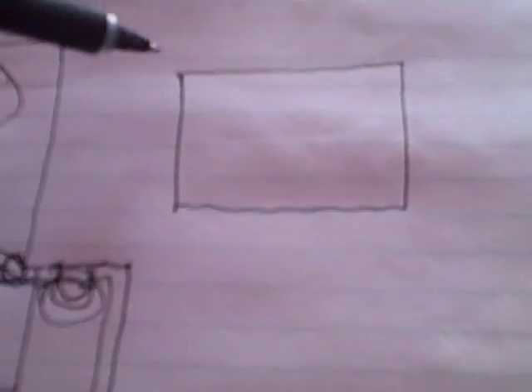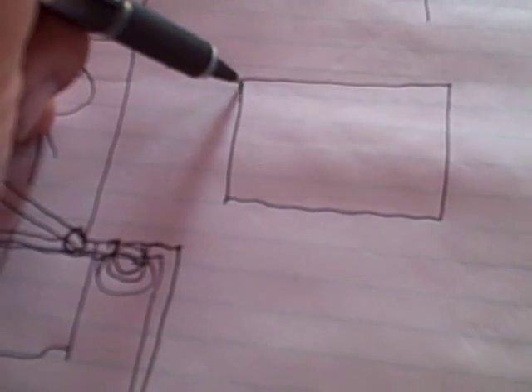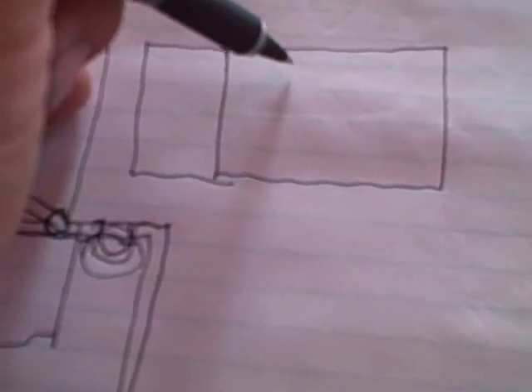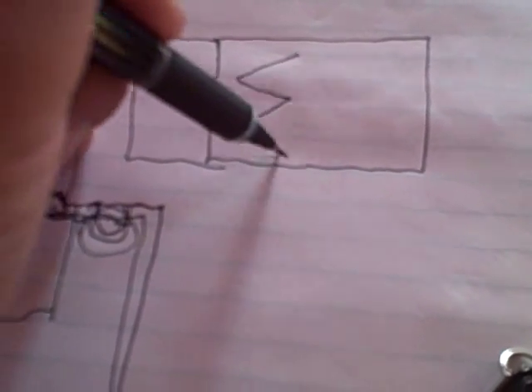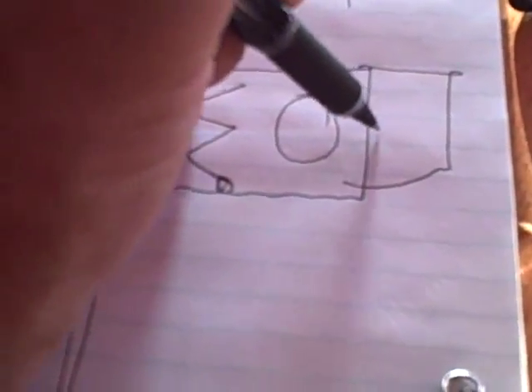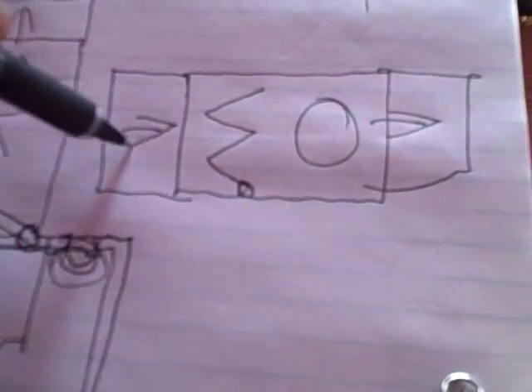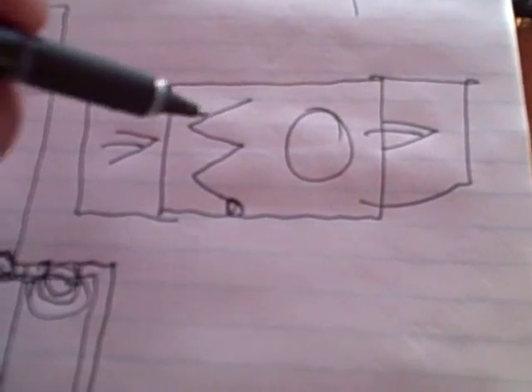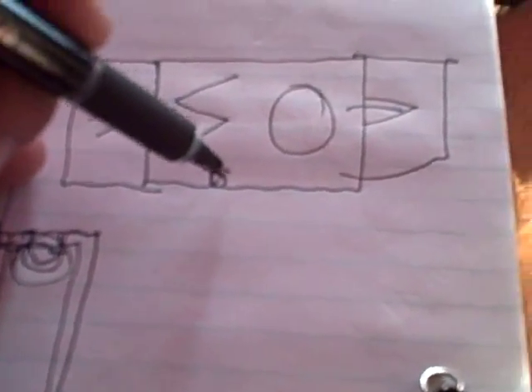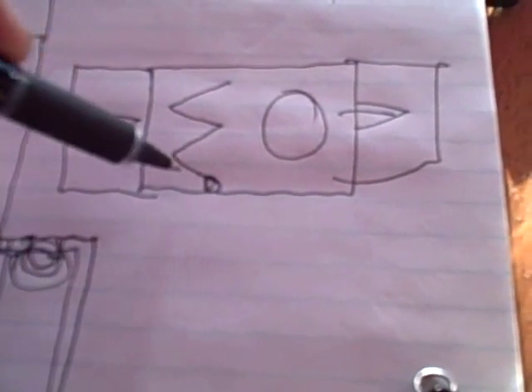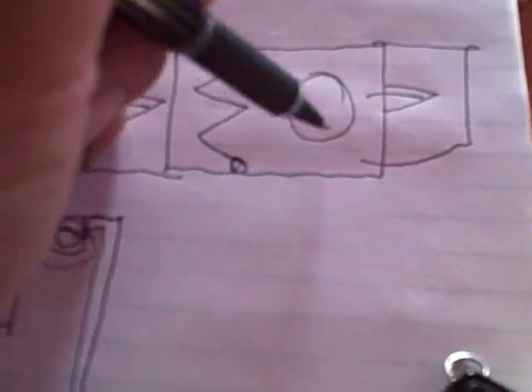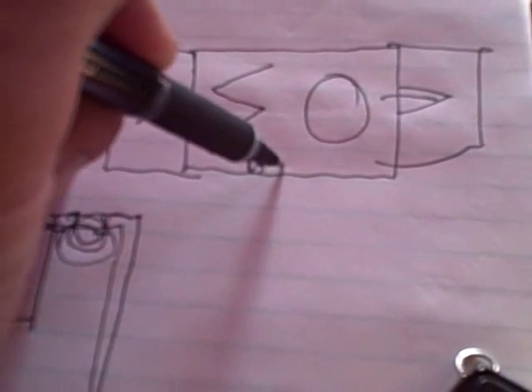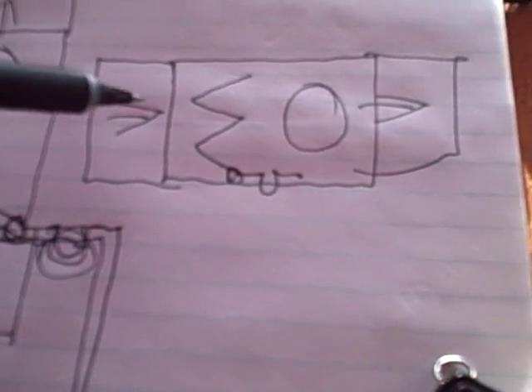It'll be the same thing in a horizontal. So in an attic you have a return duct here and an A-coil of some kind. Air drains down here, your blower's here, your supply's down here, so you've got air flowing through that way, negatively being pulled through the coil. Same thing - if you don't have a trap in the system, it physically pulls air through the drain line, so you have to have a trap here.